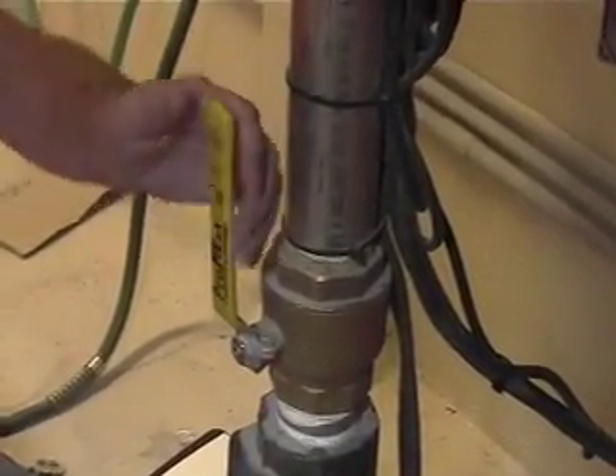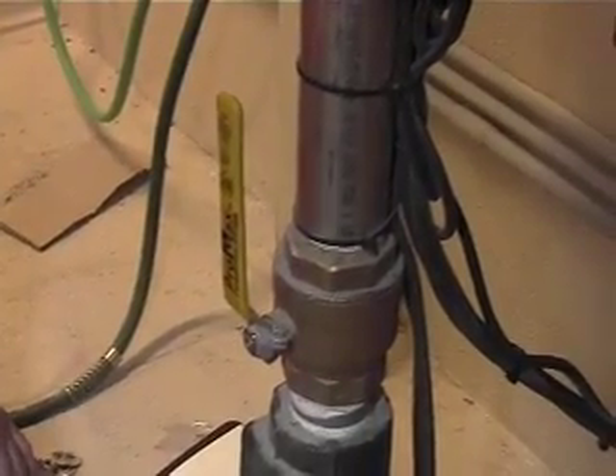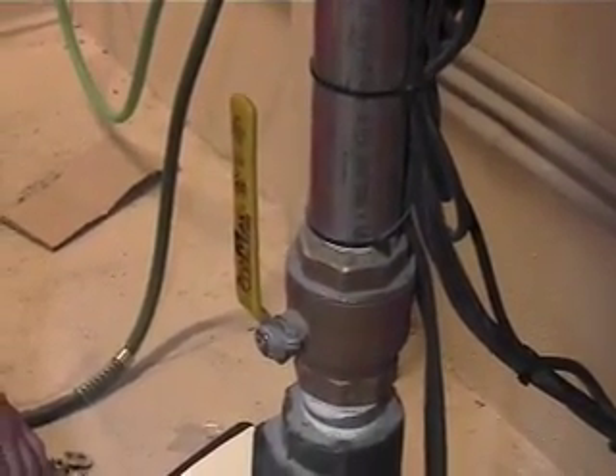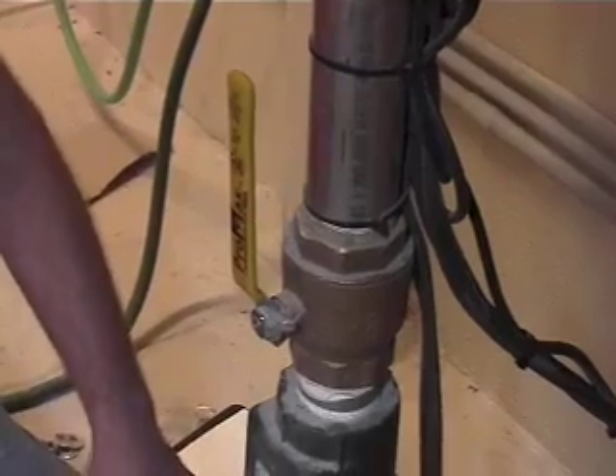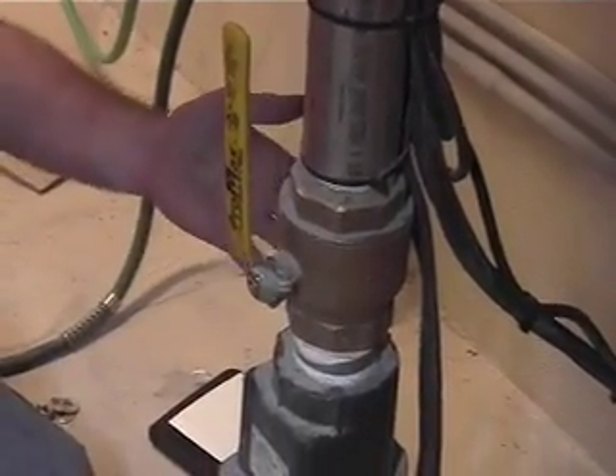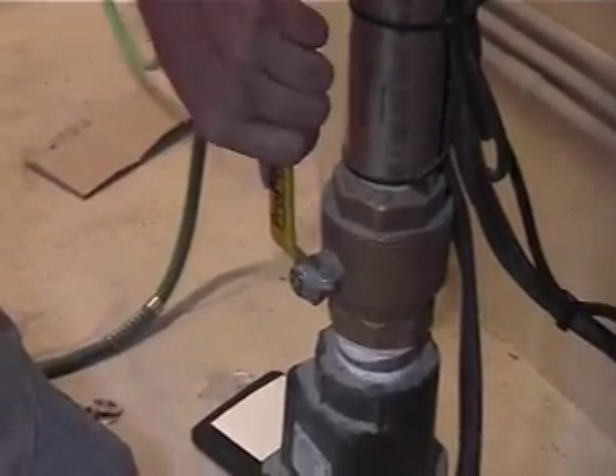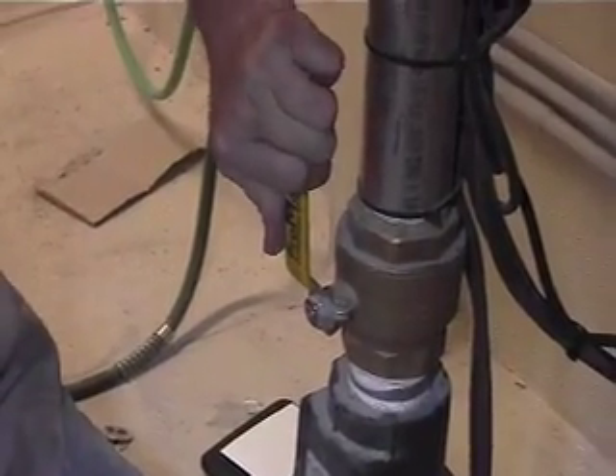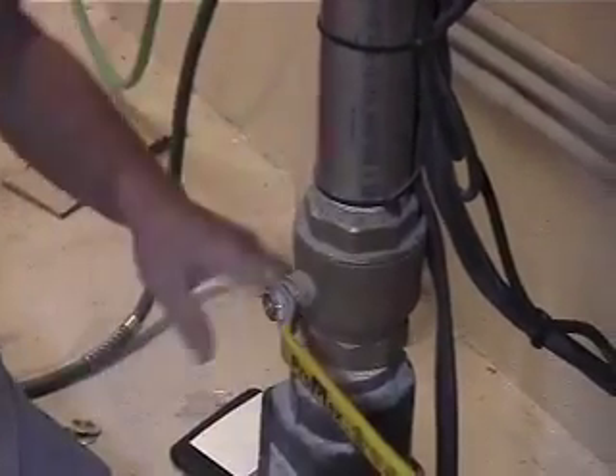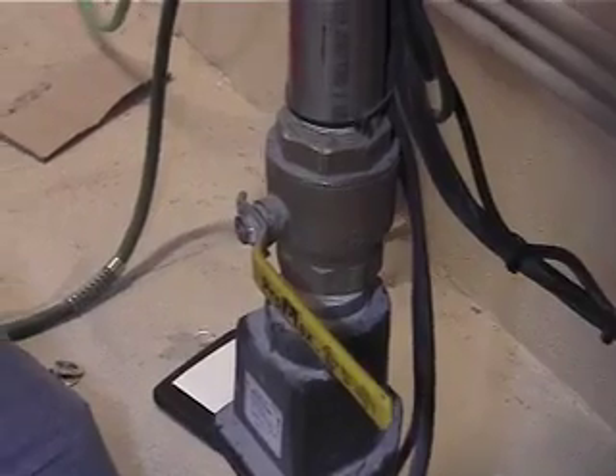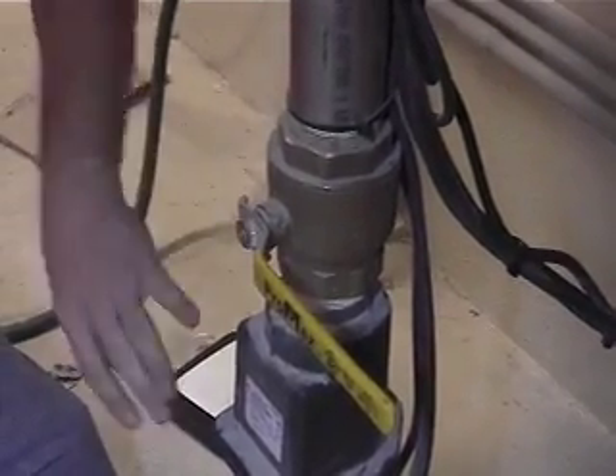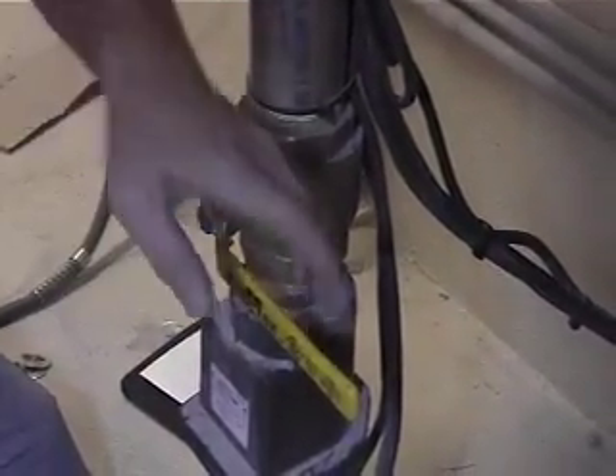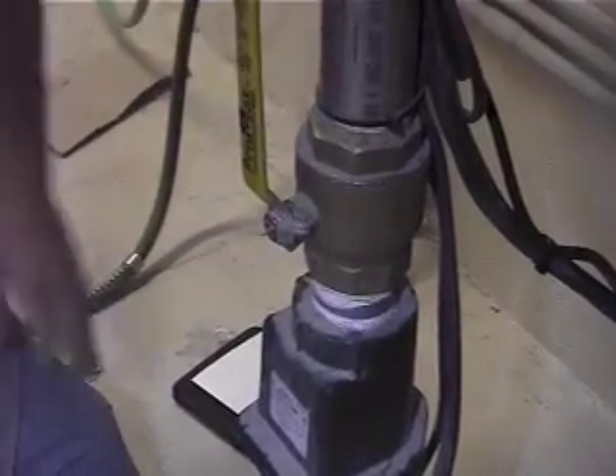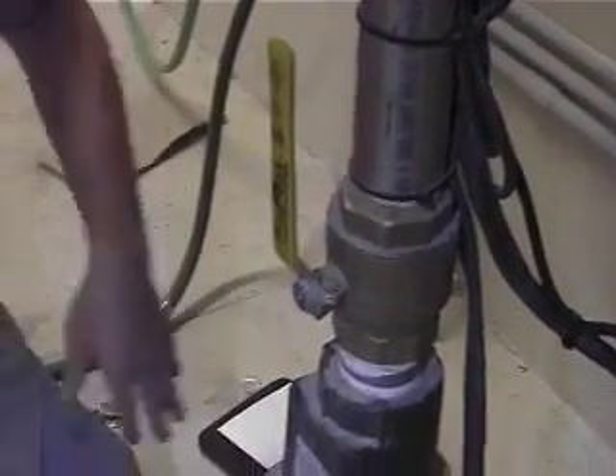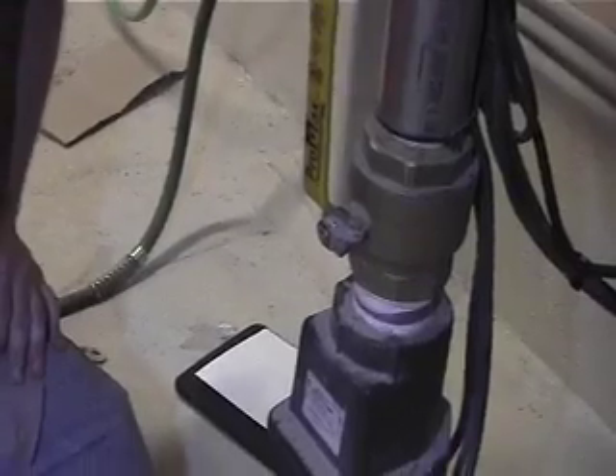This shutoff valve would shut off this line here. I guess if you had to get into this system, if you had to change out this check valve for whatever reason, you'd want to go ahead and shut that off. So then any fluid that's still in here isn't going to come back down on you. That would isolate it from coming back down and getting all over you.